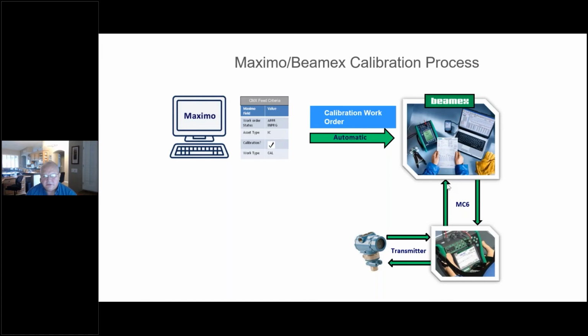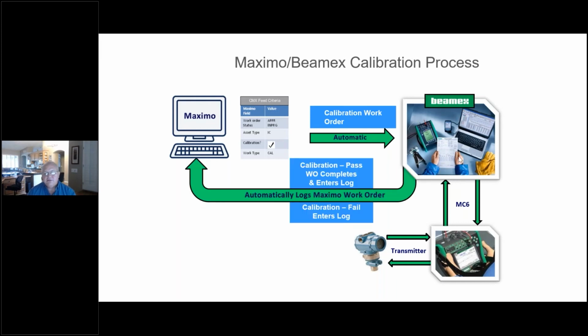This is where we get return on investment. When they go back to the shop and download their calibrations into the CMMS, all the calibrations that passed automatically get sent to Maximo. It goes to the work order built off of that route, enters a log that says calibrated via the CMMS or Beamex process, gives the logged-on user ID, and says passed. That log becomes a permanent record because it is automatically saved, and the technician never has to touch Maximo.